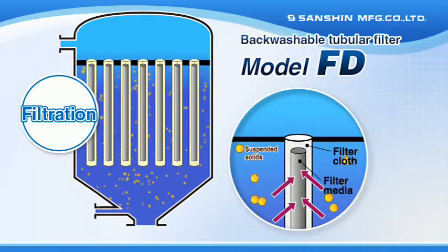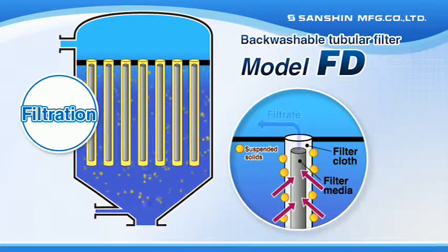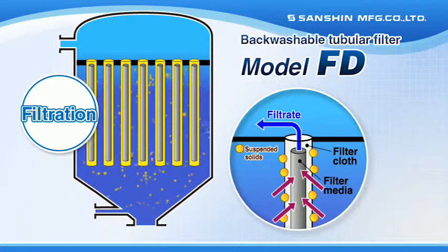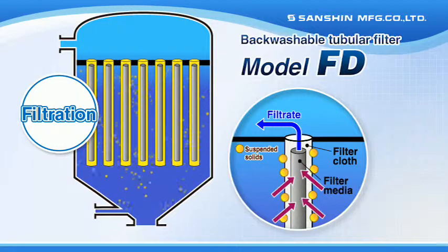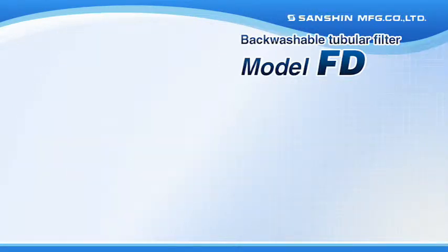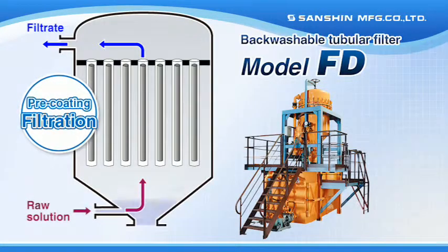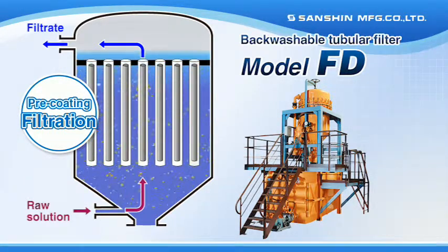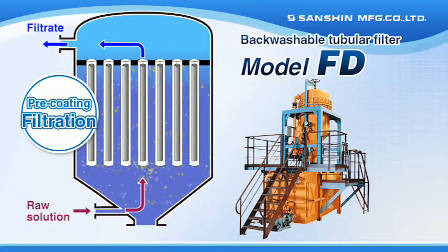Raw solution is introduced from the bottom of the filter, suspended solids are separated at the filter cloth surface, and filtrate is taken out from inside the filter media via the upper filtrate chamber. By releasing raw solution and filter aid suited to the application, filter media clogging is rare, resulting in a high-clarity, stable pre-coating filtration process.